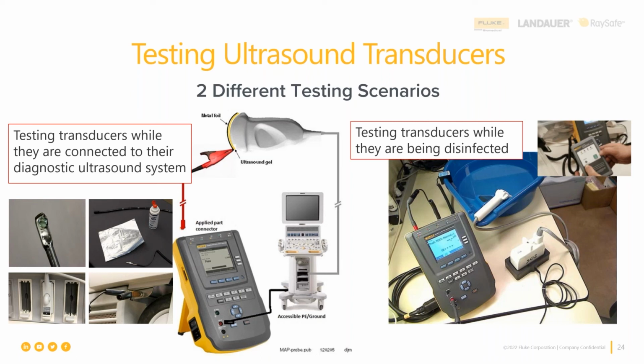So when that happens, you need to realize right behind the transducer face is 400 to 800 volts of electromotive force, EMF, that only needs a little bit of resistance to create a current flow, which is bigger than the heart's own electrical activity in terms of current. And it will interrupt that heart activity in very bad ways. So we really need to be sure that this TEE probe, connected to its medical device or not, is safe and effective for clinical use.